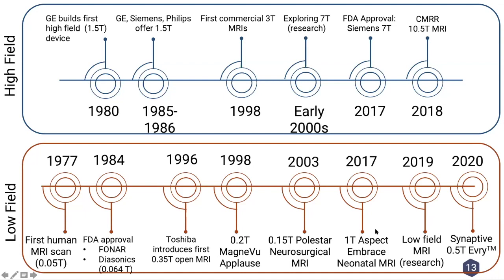I even include in this category of low field the 1 Tesla Aspect Embrace, the neonatal MRI that's out on the market. Even though it's technically a Tesla, which is higher field than a Hyperfine scanner at 64 millitesla, it's intended to be close to the neonatal intensive care unit, and has a lot of advantages compared to a conventional high field 1.5T or 3T MRI.